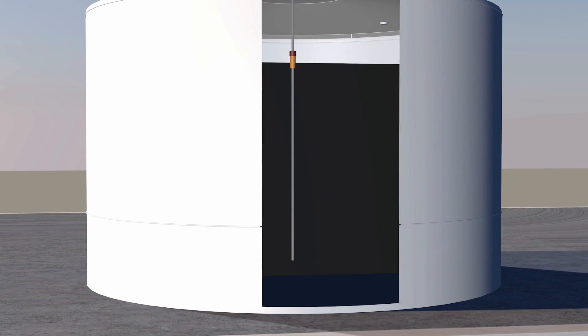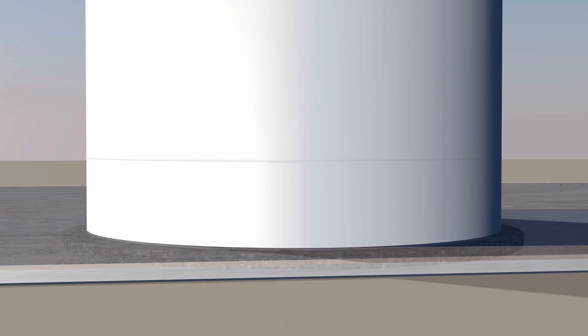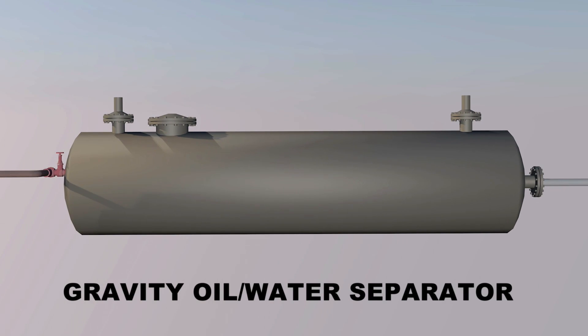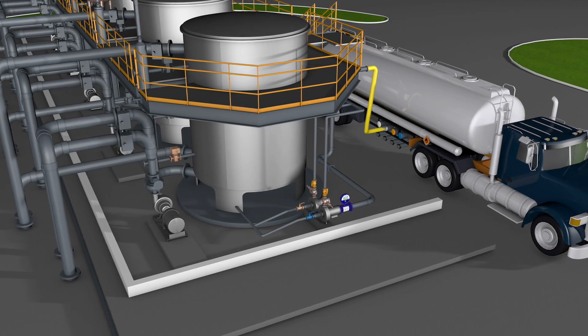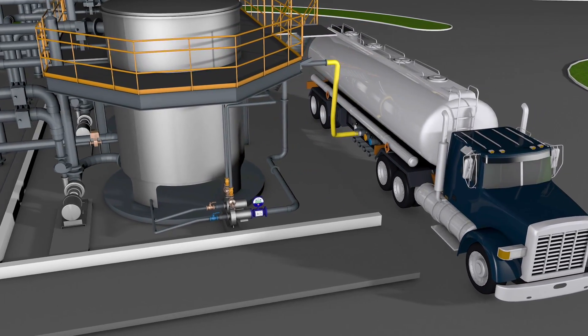Any oil that may be spilled by accidental overfilling or structural failure flows into a gravel-lined concrete trap, where it then gets flushed into a special tank called a gravity oil-water separator. Since oil is lighter than water and floats, it is easily trapped behind a vertical barrier or baffle where it can be recovered and placed back into storage.